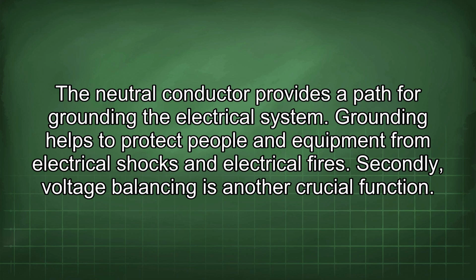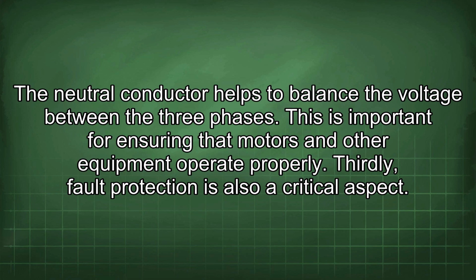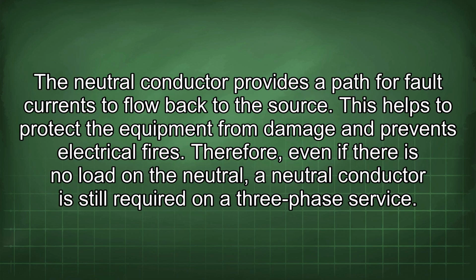Secondly, voltage balancing is another crucial function. The neutral conductor helps to balance the voltage between the three phases. This is important for ensuring that motors and other equipment operate properly. Thirdly, fault protection is also a critical aspect. The neutral conductor provides a path for fault currents to flow back to the source. This helps to protect the equipment from damage and prevents electrical fires. Therefore, even if there is no load in the neutral, a neutral conductor is still required on a three-phase service.